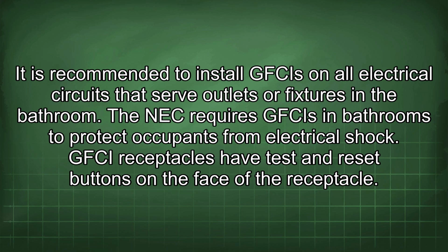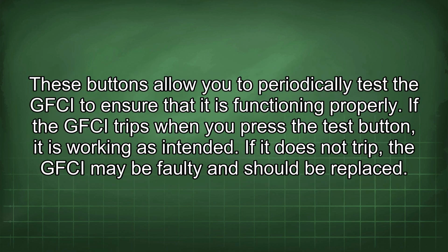GFCI receptacles have test and reset buttons on the face of the receptacle. These buttons allow you to periodically test the GFCI to ensure that it is functioning properly. If the GFCI trips when you press the test button, it is working as intended. If it does not trip, the GFCI may be faulty and should be replaced.